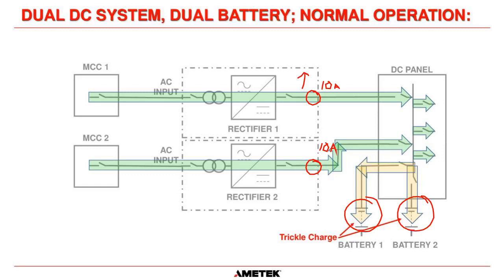So I know that's a very long-winded conversation about load sharing. I personally don't think that it is necessary. You are messing about with the end terminal voltage at the batteries, which is not what you want to do. And people forget that. And you will, in most cases, either overcharge one of the batteries or undercharge one of the batteries, unless you size the cables absolutely perfect and the temperature in the battery room at both batteries is identical. There are so many parameters that affect load sharing.